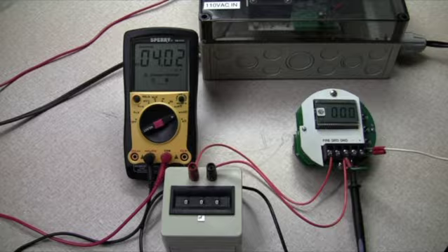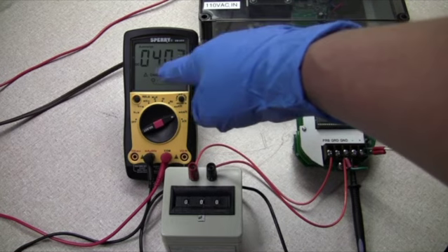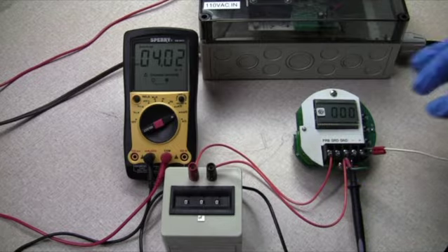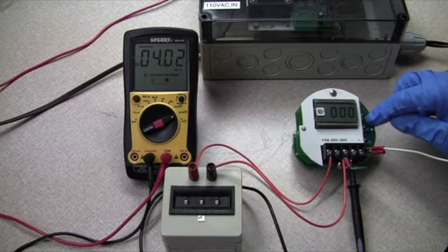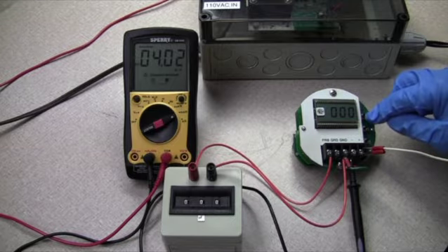So the first step is calibrating your 4 and your 20. The 4 and the 20 is very important. Right now, as you can see, it's already calibrated as we have 4.02. It could be 3.86, it could be 4.19, and this is how you're going to set up your 4 to 20. So these three buttons are what you're going to use to calibrate the unit. Set your high and your low and your 4 to 20.